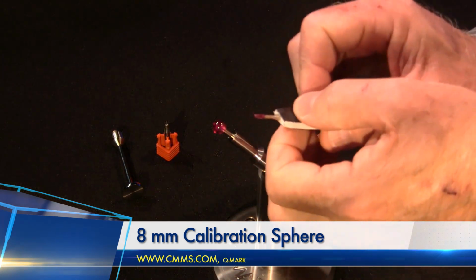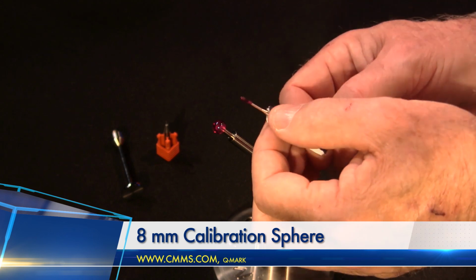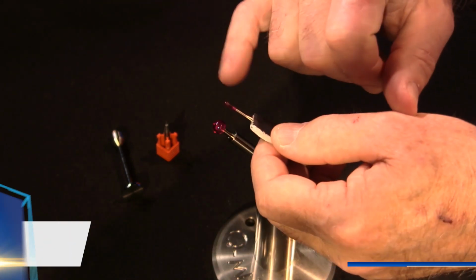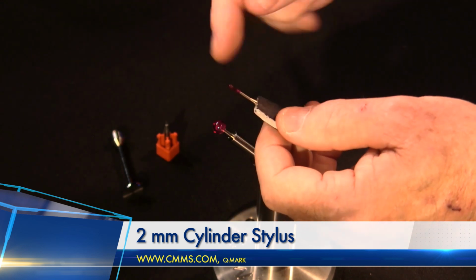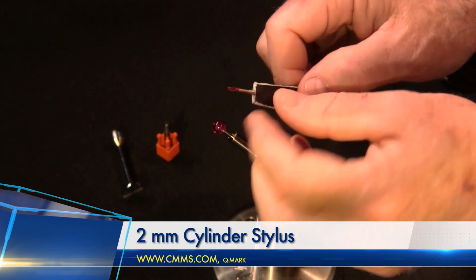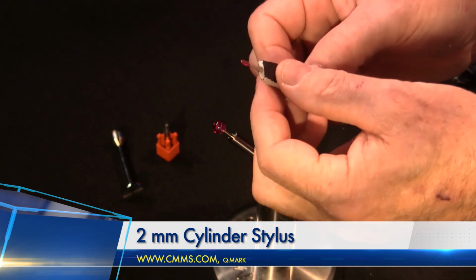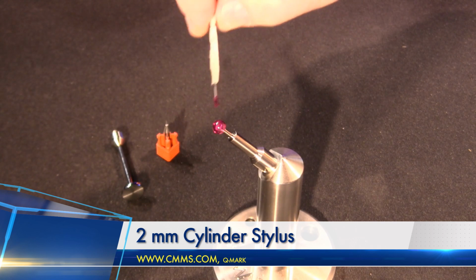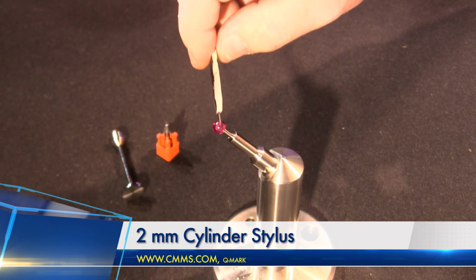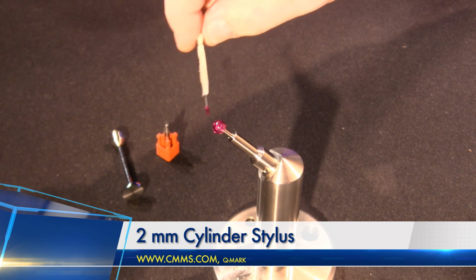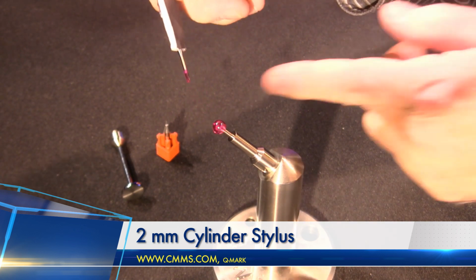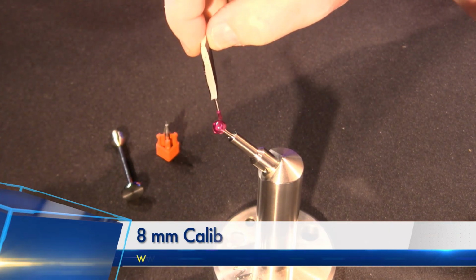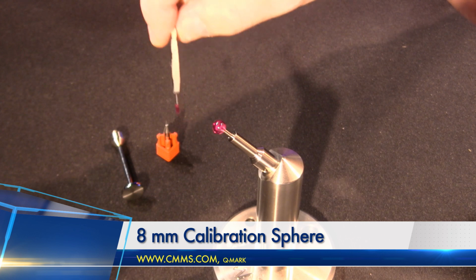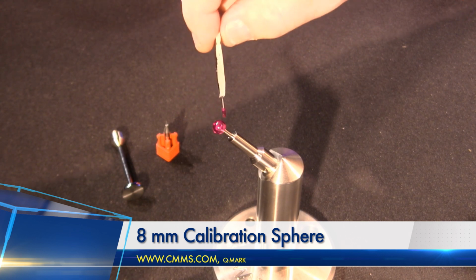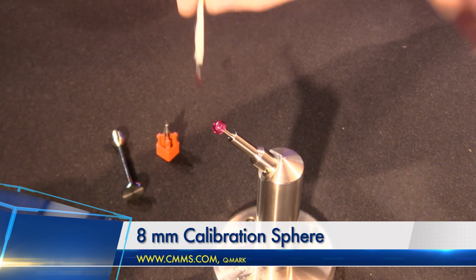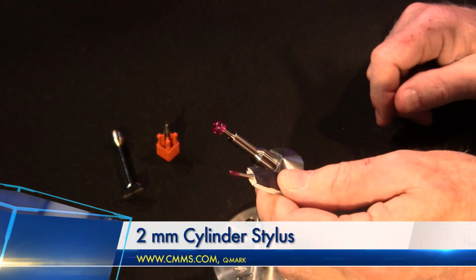And finally, what I have here, again stuck in a piece of styrofoam so I can hold on to it, is a cylindrical probe. So notice that the ruby tip here is a cylinder with a curved end on it. That curved end is not a perfect hemisphere. And that's important to note because when you go to calibrate a cylindrical probe, you have to make sure that you do not approach your calibration sphere at 180 degrees, because if you do, most likely the curved tip of the probe will not contact the curved edge of the calibration sphere. So what you really want to do is come in at about 150 degrees. At 150 degrees, you're going to take your measurement points and again use that data to calibrate your cylindrical probe.